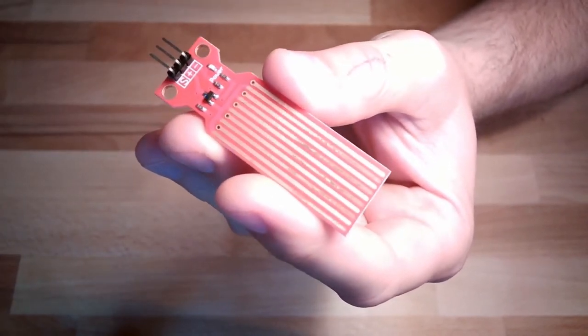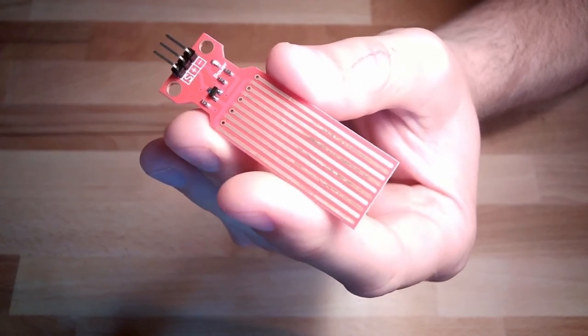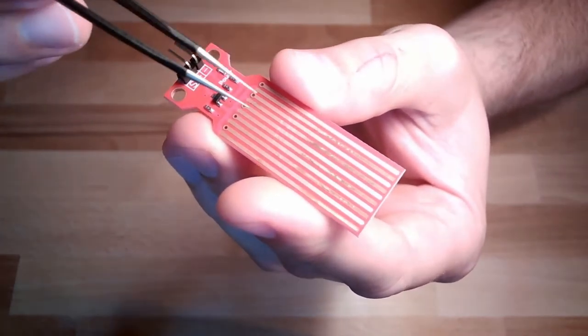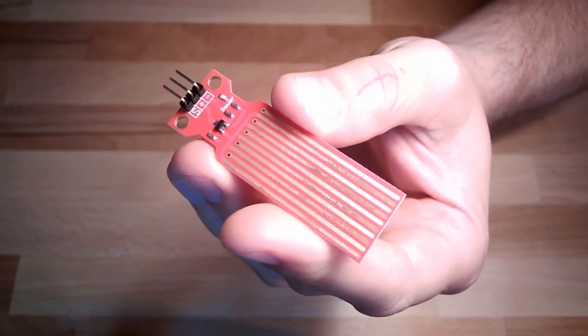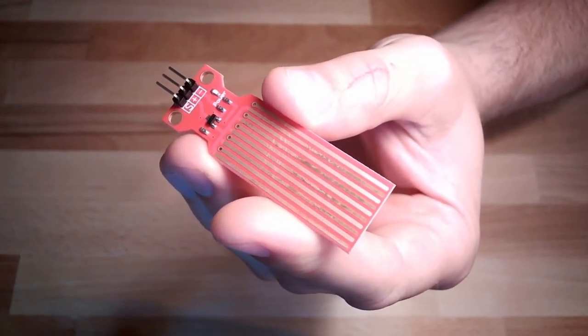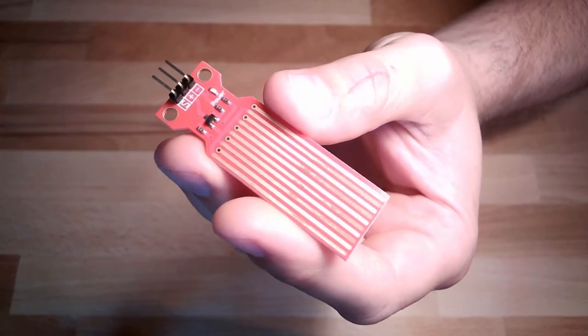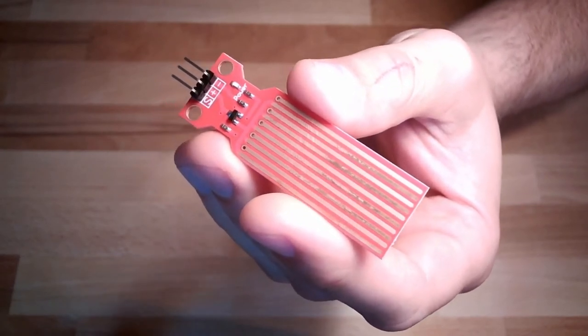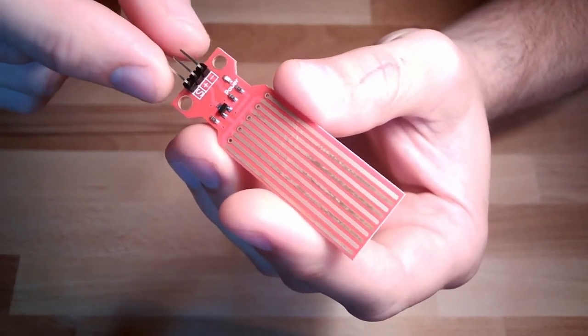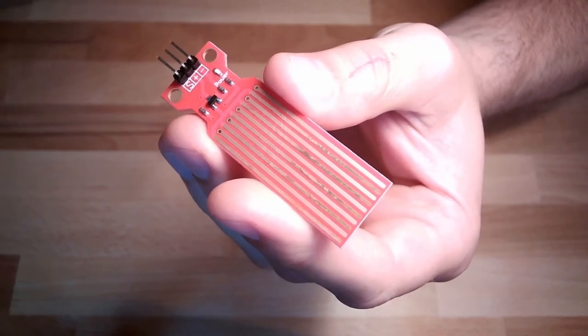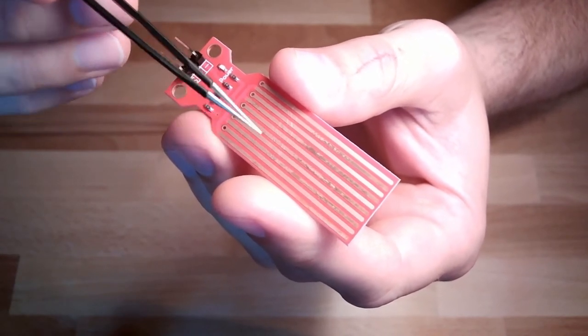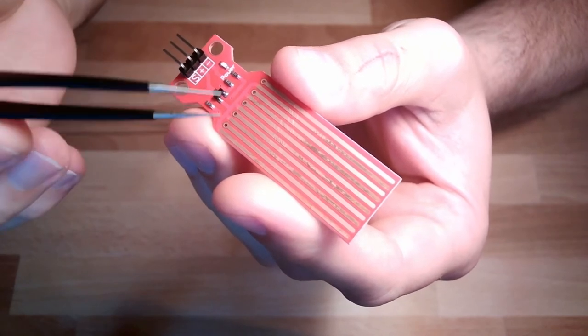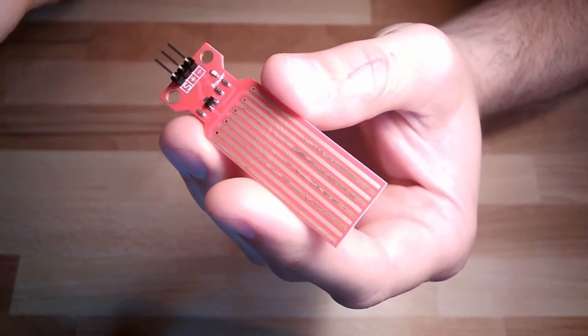And you can see that the copper things are getting dissolved over time. That's an issue with such kind of sensors. They simply will go away, dissolve in the liquid which is covering them, because it's ionic current. And then, of course, there is another resistance anyway, causing a drift on this type of sensors.